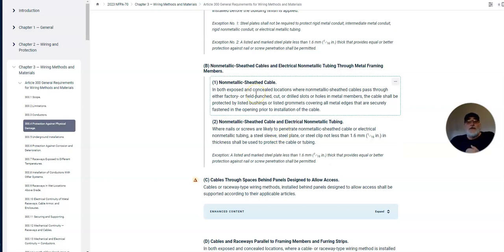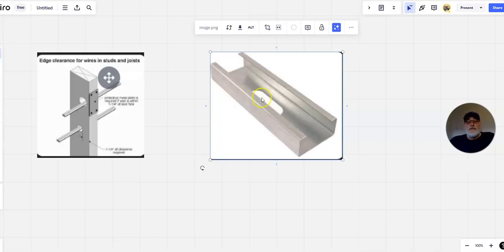Let's read this. Non-metallic sheath cables and electrical non-metallic tubing through metal framing members. Okay, now what is a metal framing member? Here's an example of a metal framing member right here. Metal stud buildings, commercial buildings, 98% are built with this. This over here is an example of a wood build where you have your non-metallic cable protected, and this one's 1.25 further back. That's just showing your 1.25. Now, mind you, that's talking about that hole right there, the edge of the hole out to the front.